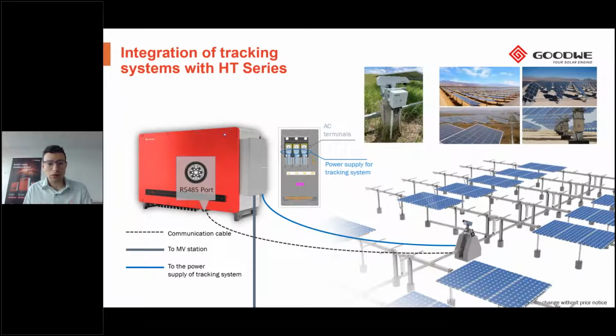Panels also drive the popularity of tracking systems. In the past, there was barely a link between inverters and tracking systems. Now, with the string inverters getting closer to the tracking system itself, we start establishing communication between the inverters and the tracking systems in order to integrate things into one monitoring system, but also to give power supply to the tracking system, not only from the panels, but also from the AC side, which allows for easier maintenance and also operation by night or under snowfall, as an example.